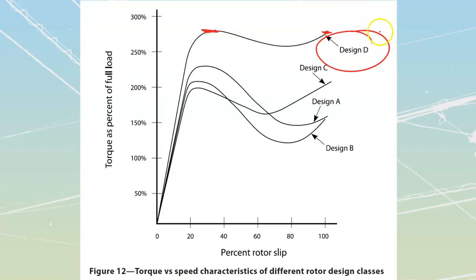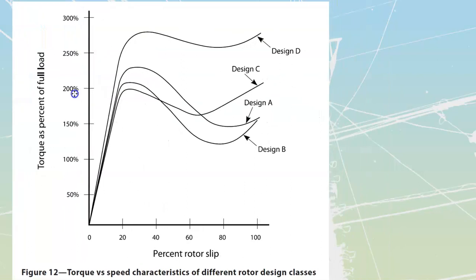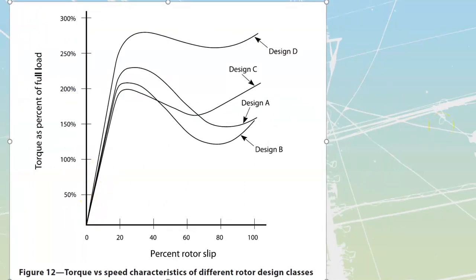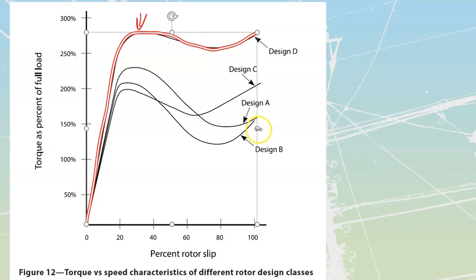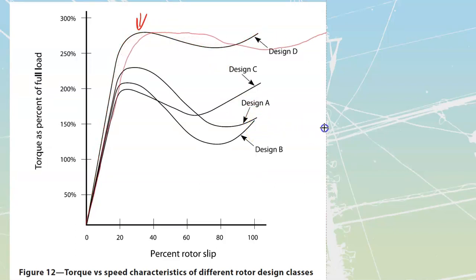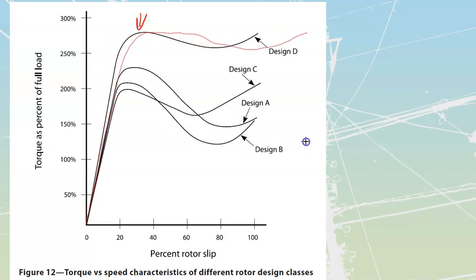Design class D was characterized by having a high resistance type of rotor. What we're going to do with the wound rotor motor is take a design class D motor and do something really special with it. We're going to have a high resistance rotor giving us this overall torque curve, and by selectively applying components we'll be able to adjust where the peak is. I'm going to stretch this waveform out and move where we get our maximum torque.